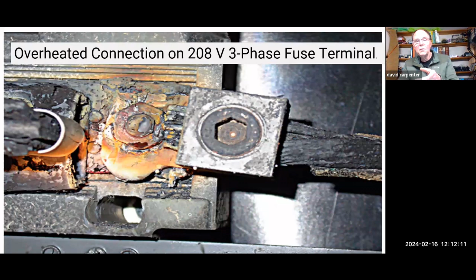This right here is an overload, but torquing is a requirement, and I see this quite often. They don't torque. I can tell you about buses that have blown up, they hadn't torqued them in 50 years, hadn't checked the torquing on them.